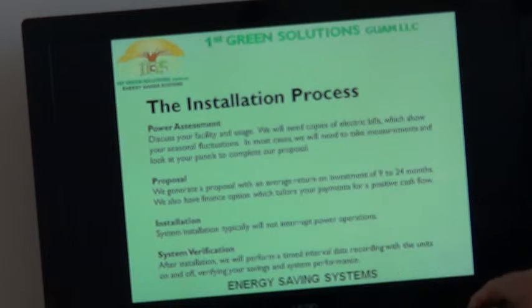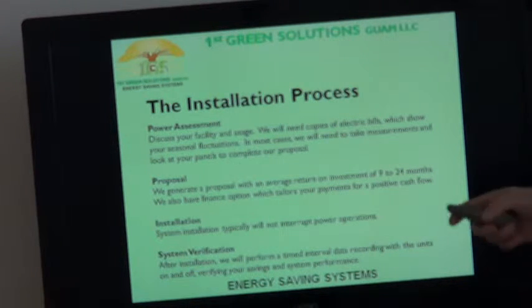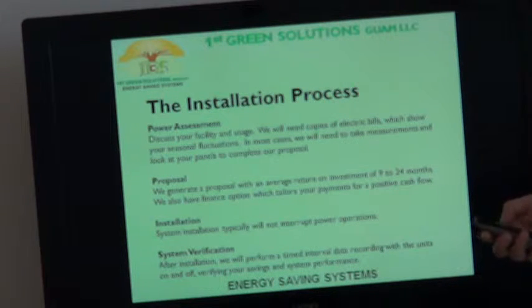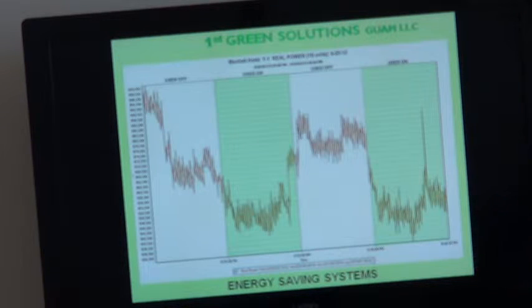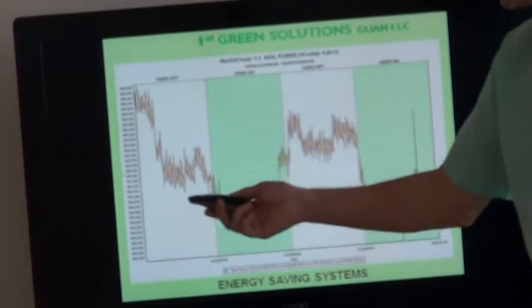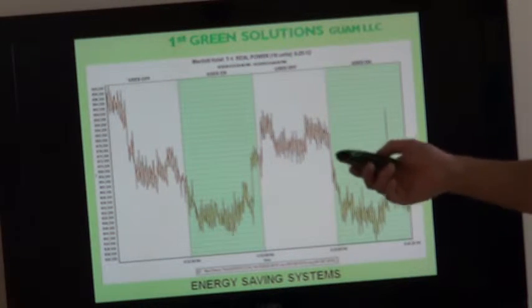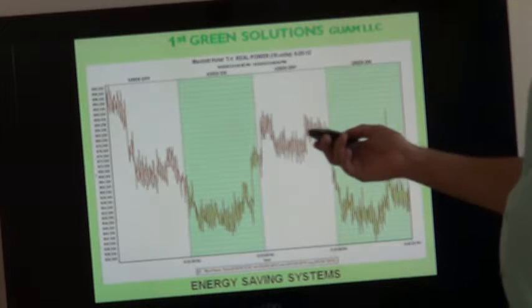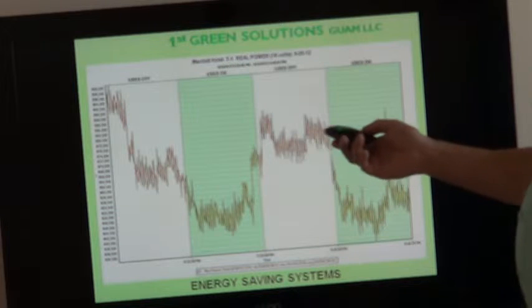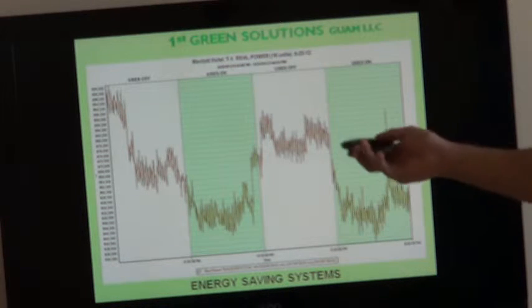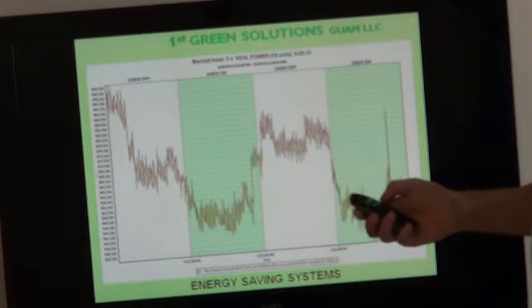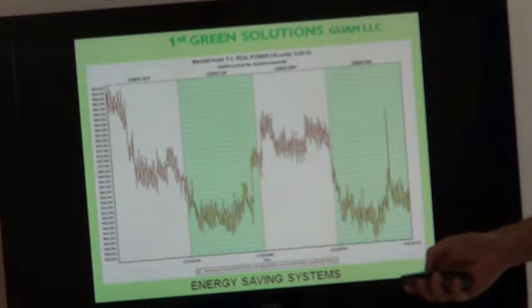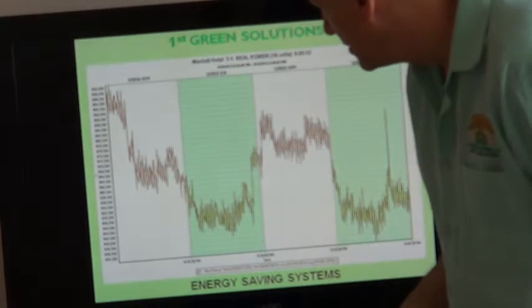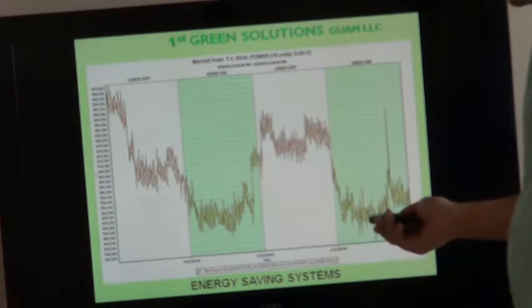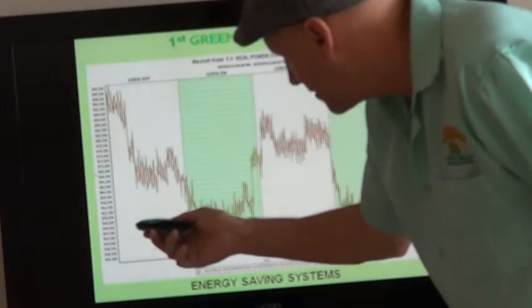This is a way for us to take timed interval data recordings with the usage units turned off and on at precise intervals. In this case, this is the Marriott Hotel. We're turning the usage units on and off in precise 5-minute intervals. So this is their power consumption up at this level when the usage units are off, and when the usage units come on, their consumption's down here. This graph is for kW, which is measured by the utility company as power consumed. We're going from 876,000 average down to 846,000, which is roughly a 30,000 savings.